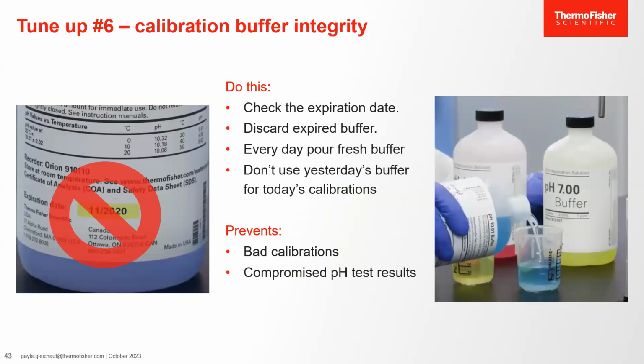Tune-up number 6, calibration buffer integrity. Check the expiration dates and dispose of expired buffers. Every day, use a fresh pour from a bottle of properly stored, non-expired buffer. Don't use yesterday's buffers for today's calibration. Prevent bad calibrations, because compromised buffers will compromise pH test results.